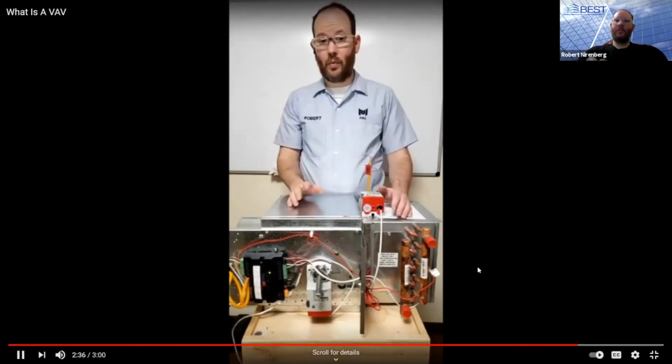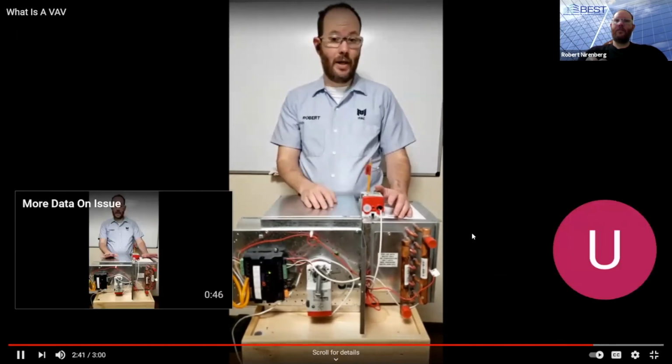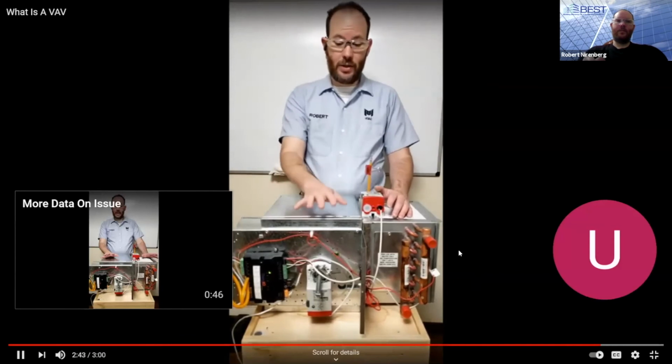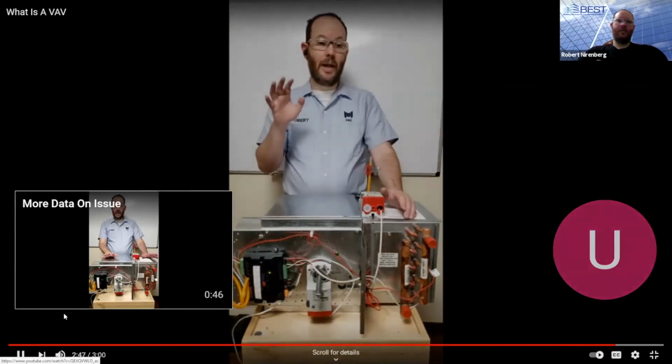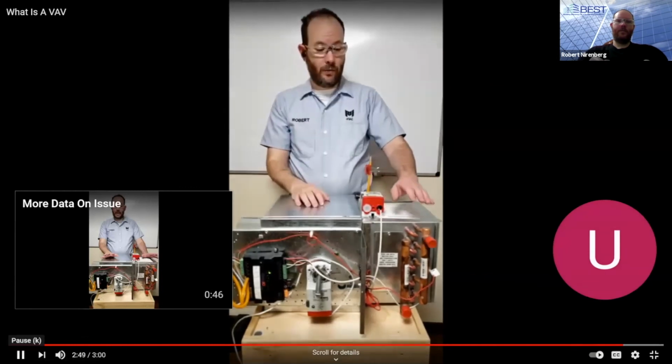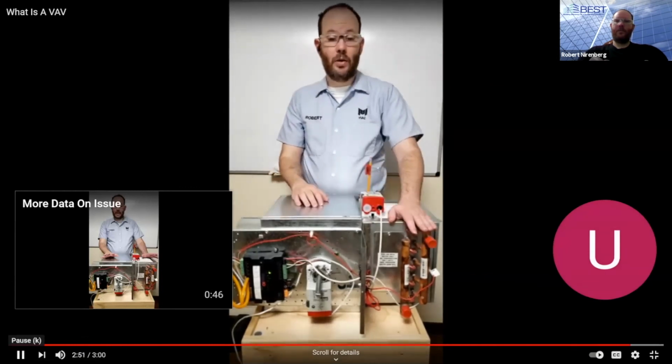There is a third set point that is frequently used, which is a reheat CFM, and that controls the system to a specific CFM and eliminates the airflow variable for heating modes.